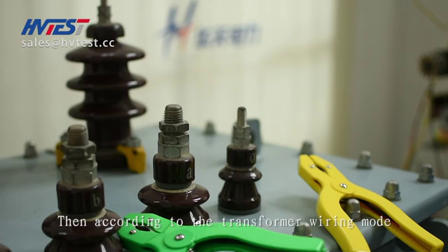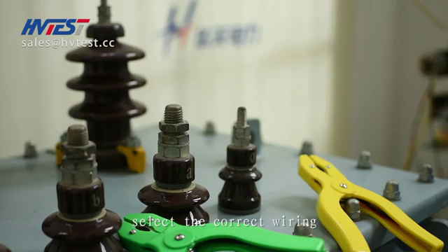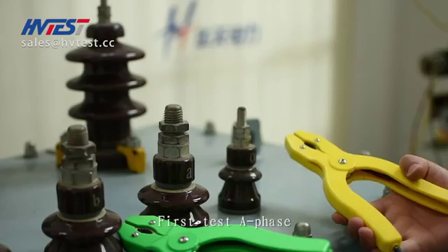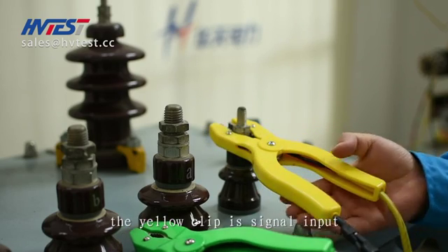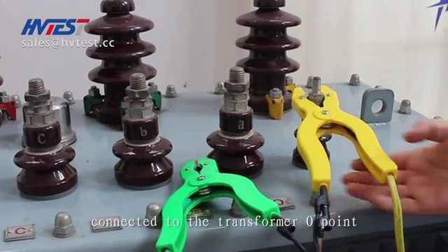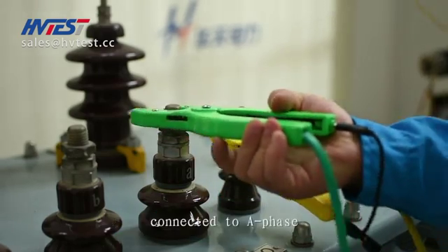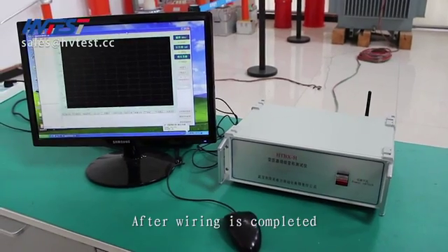Then, according to the transformer wiring mode and the wiring diagram in the instruction manual, select the correct wiring. After finished wiring, we are ready to test. First test the A-phase. The yellow clip is the signal input connected to the transformer O point. The green clip is the signal connection connected to A-phase.